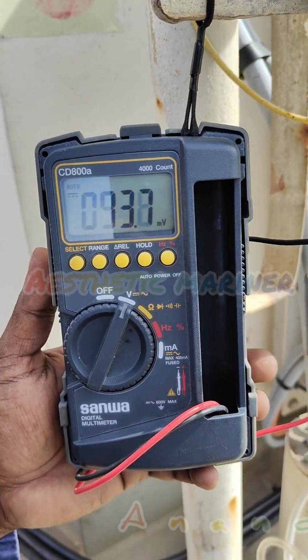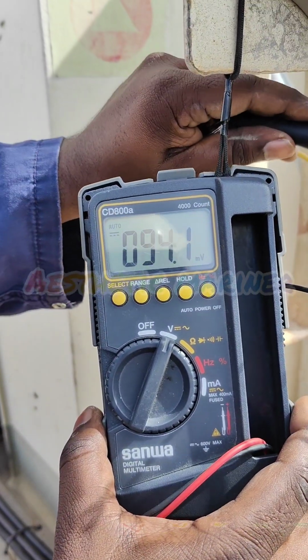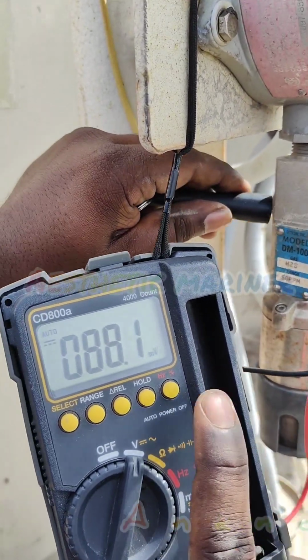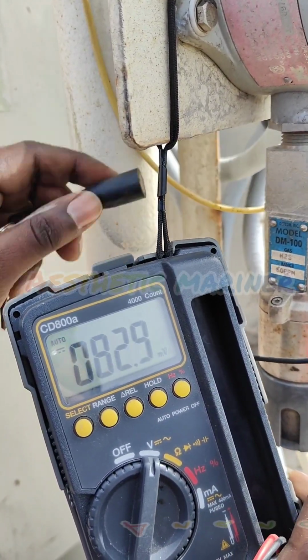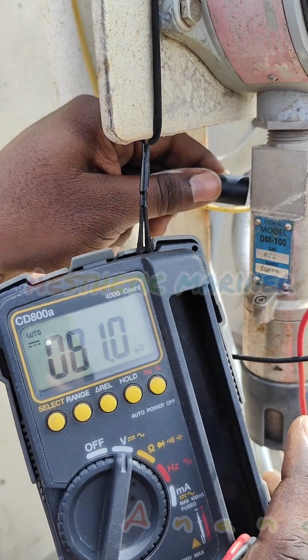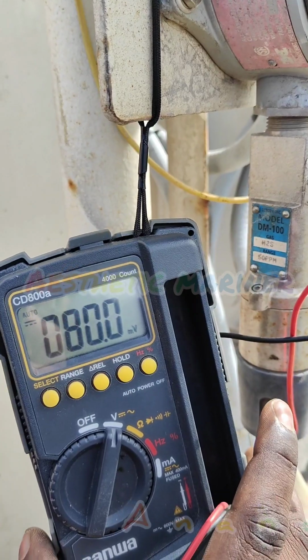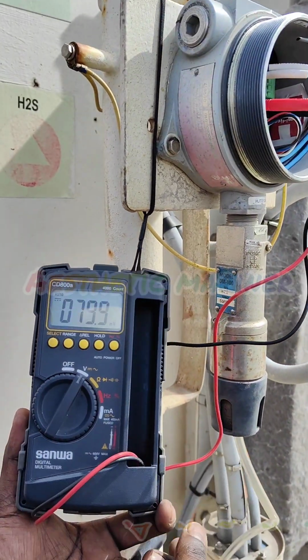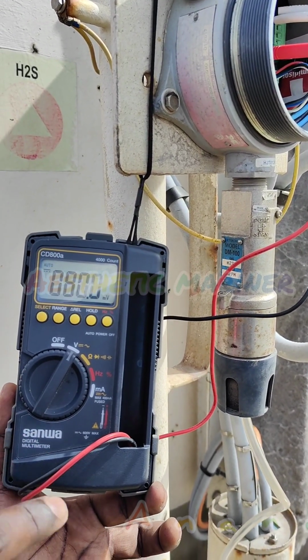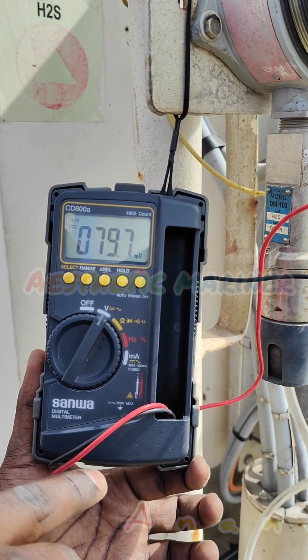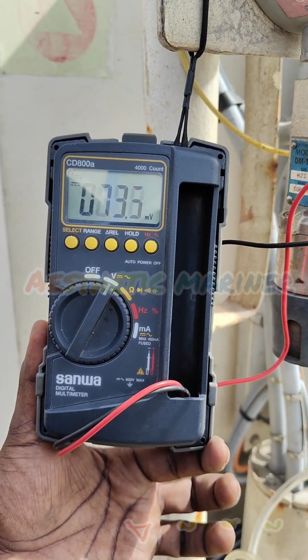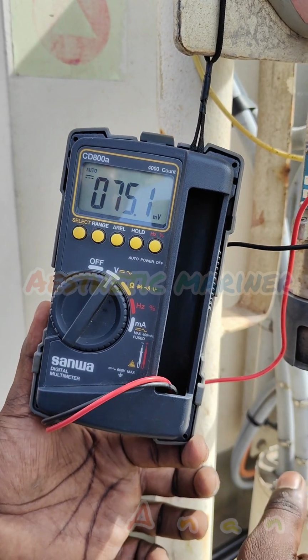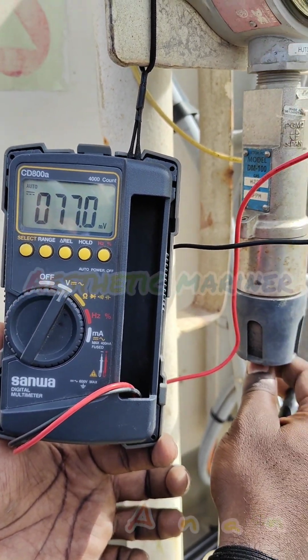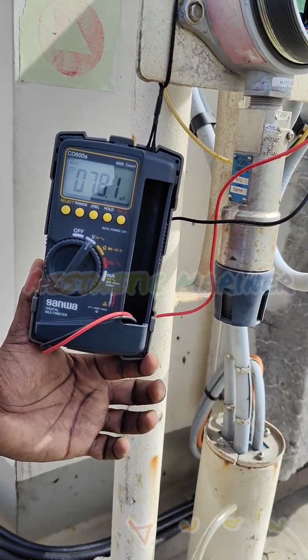Now the 2 minutes are already over. Here we can see the reading has come, and it reached 94.1 millivolt. I need to set it to 80 millivolt, so I am pressing PG1 to reduce the span reading. Now you can see it is decreasing towards 80. Once it reaches 80, we just need to wait for some time. Then it will decrease again by 10%, and then suddenly it will increase. That is when we know the span has passed. Now the reading has suddenly changed, and we know the span calibration has passed. So we can remove our calibration gas. Now the span value is set to 80 millivolt.